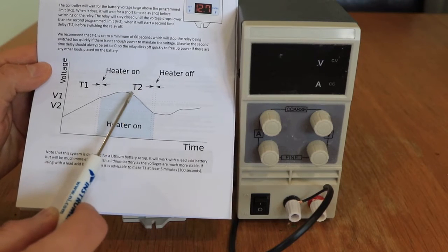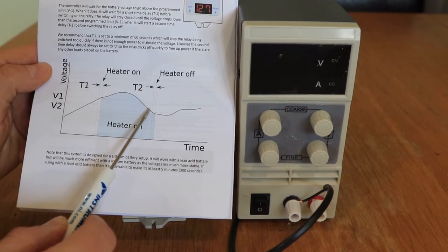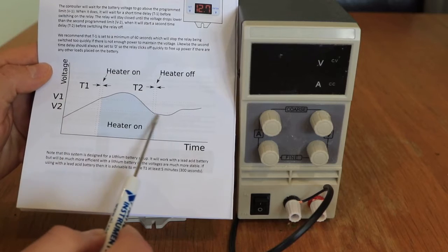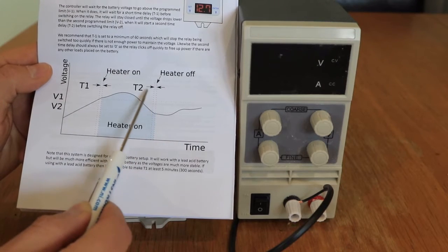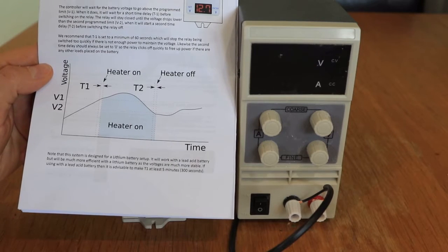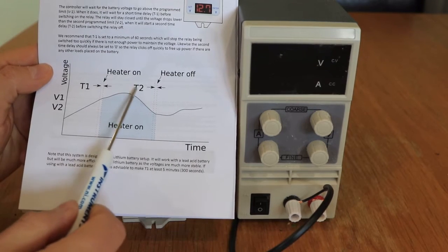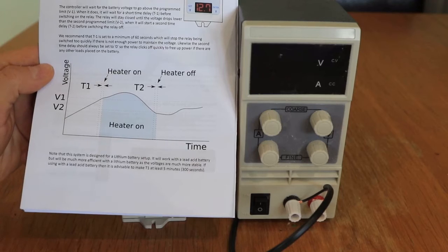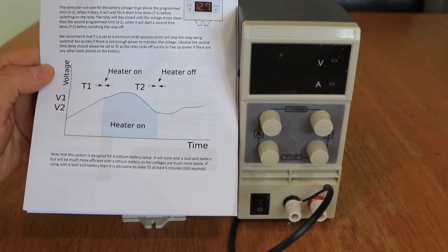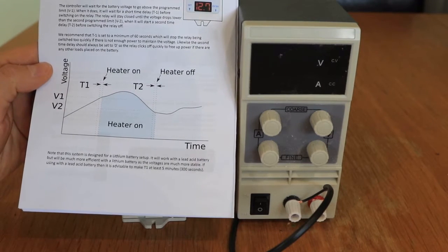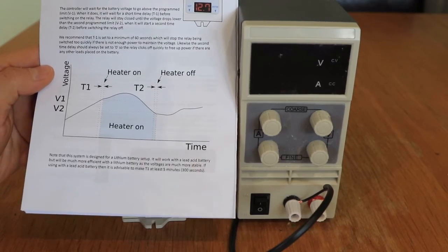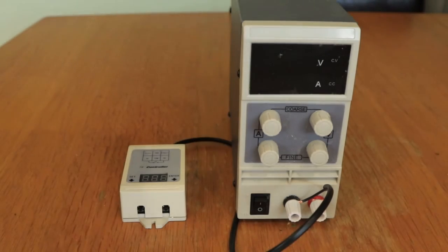That starts to run out whilst the heater is still on. It then gets down to our turn off voltage, which is V2. That triggers another time delay, and then after that time delay the relay turns itself off. Now we always recommend that this T2 is set to zero. Everything else can be configured to your setup and there's a lot more information about that on our website. If you go to the Solaris page, it's all there as a download.